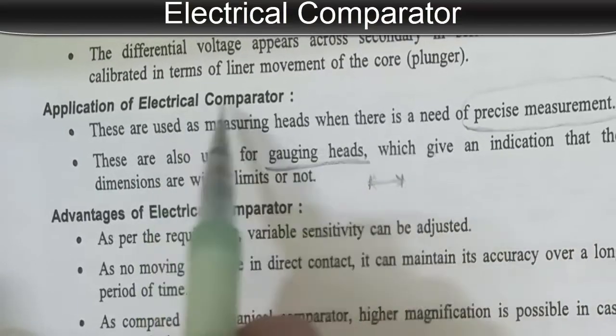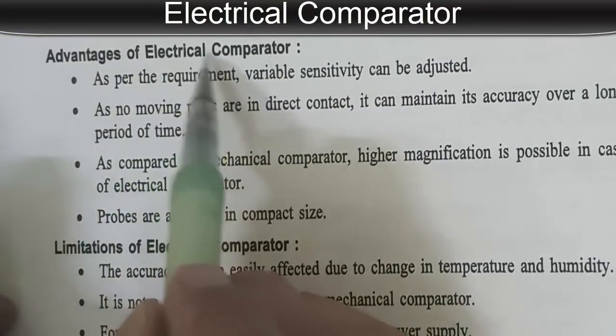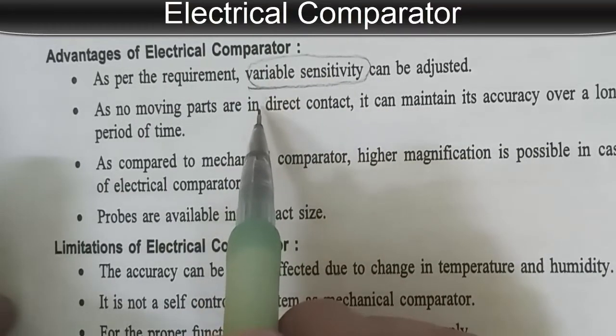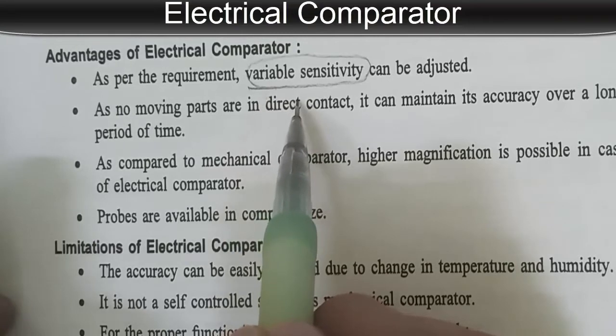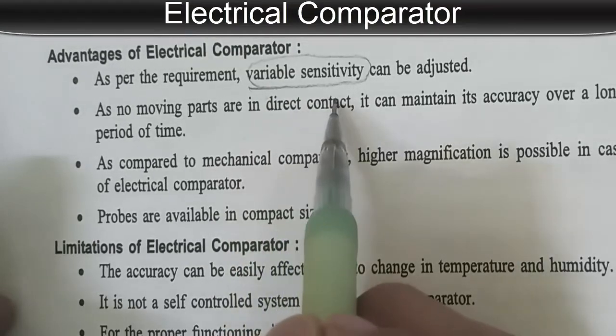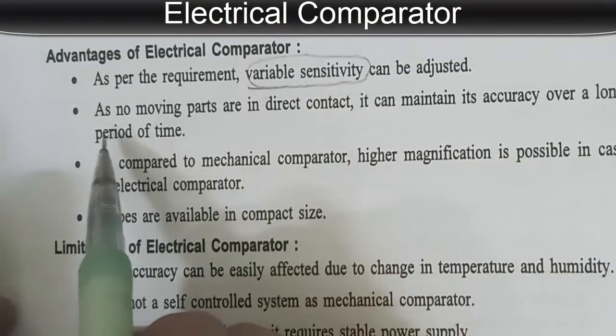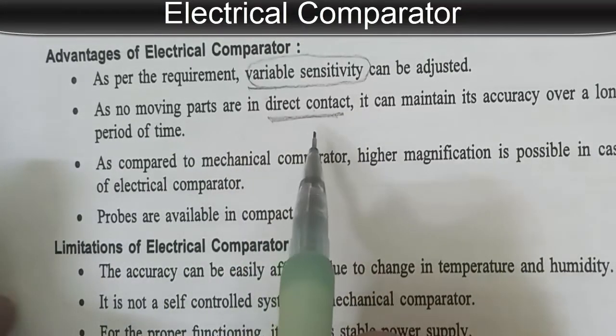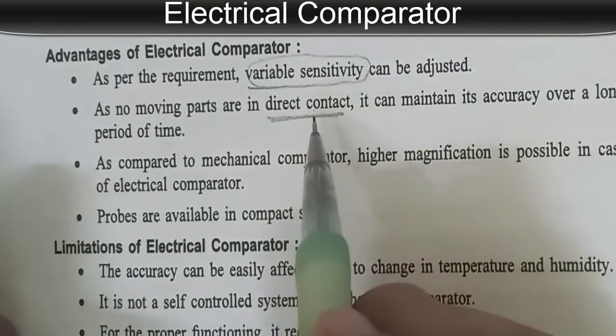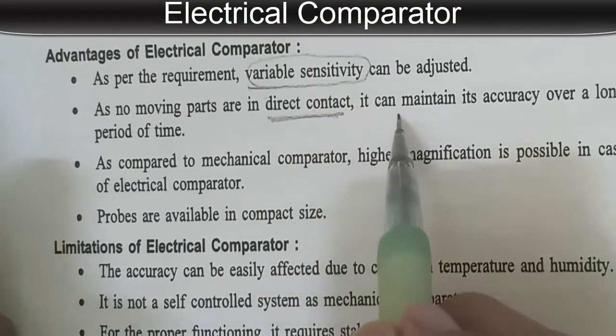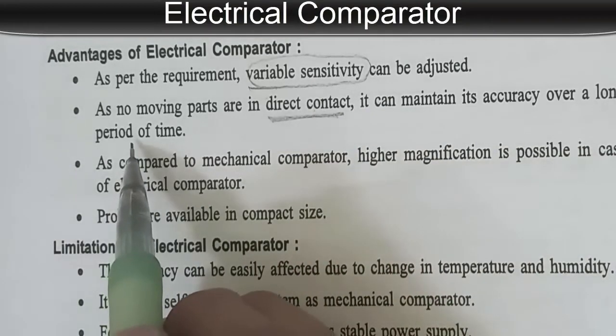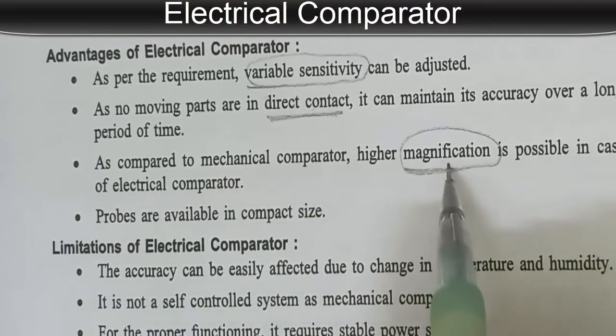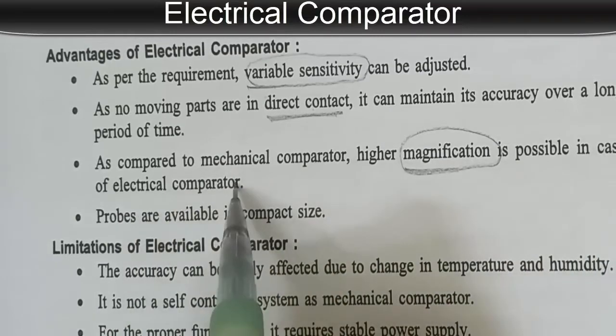Advantages of the electrical comparator: variable sensitivity can be adjusted as per requirement — sensitivity means for a particular input, what should be the output, and that we can adjust. As there are no moving parts in direct contact, the core moves inside but does not touch, so there is no direct contact of moving parts, and it can maintain accuracy over a long period of time. Higher magnification is possible as compared to a mechanical comparator, and probes are available in compact size.